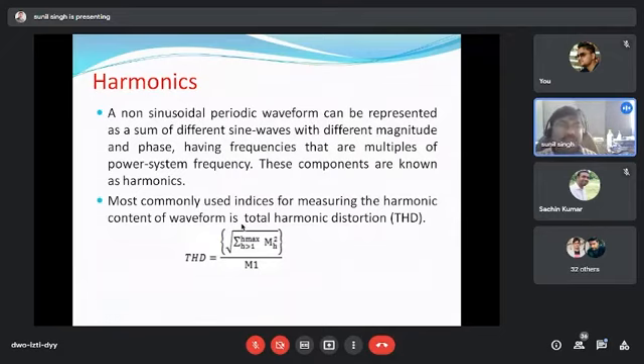Harmonics means our waveform deviates from the sinusoidal and becomes non-sinusoidal. A non-sinusoidal waveform can be represented as a sum of different sine waves with different magnitudes and phases, having frequencies that are multiples of the power system frequency. These components are known as harmonics. What does it mean? If the waveform is not purely sinusoidal, then a contaminated or non-sinusoidal waveform can be decomposed into various sinusoidal waveforms having integral or multiple frequencies.